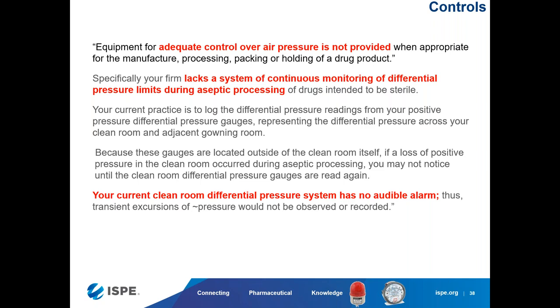We do have Magnehelic devices at the door, sometimes we're still doing manual notation of the pressure differential, but at the door that does not help us because the operator should know. And that is why, for continuous monitoring, we invest a lot in continuous monitoring systems, but we don't integrate it with our BMS system, which is very important.